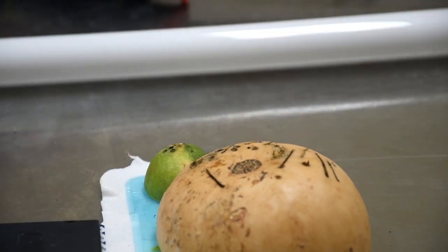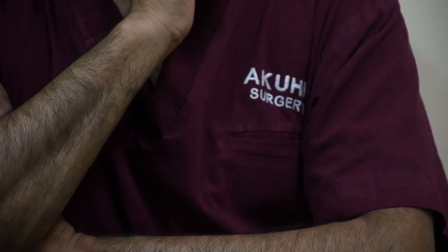So where would you use fulgurate? If you have a raw surface that actually is oozing, let's say on the uterus, on the liver, then you would use a fulgurate or a spray to spread the superficial burning, and you can use the blue directly with a direct instrument because you want to cause a superficial surface burning. So it doesn't go deep, but it burns the superficial area very quickly, and that will stop the oozing. But when you want to hold vessels and burn vessels, and you have to be very careful, use the cut mode, the yellow, do not use the blue.